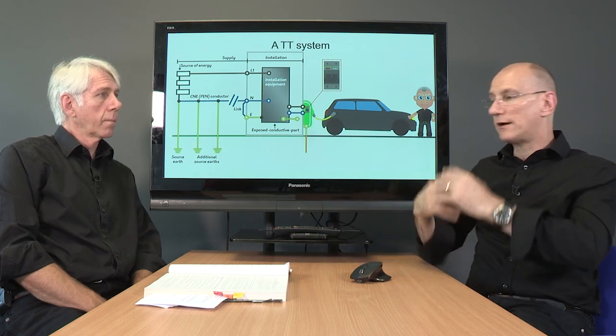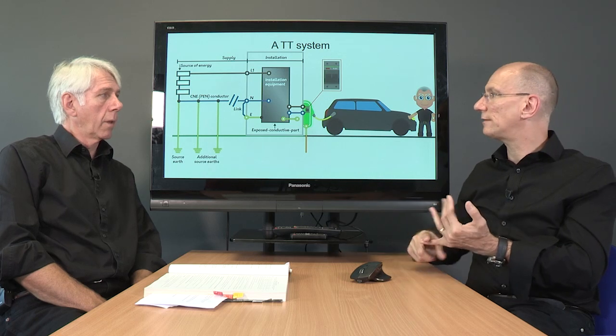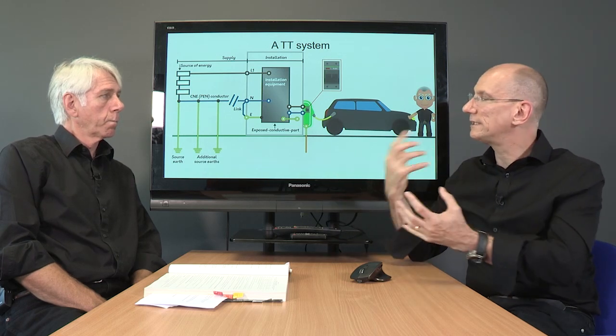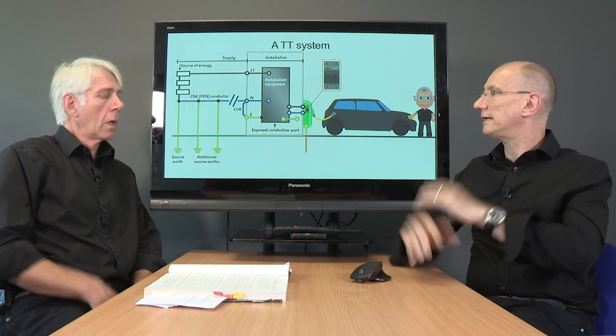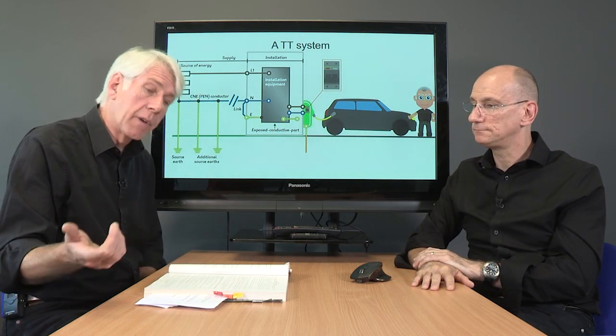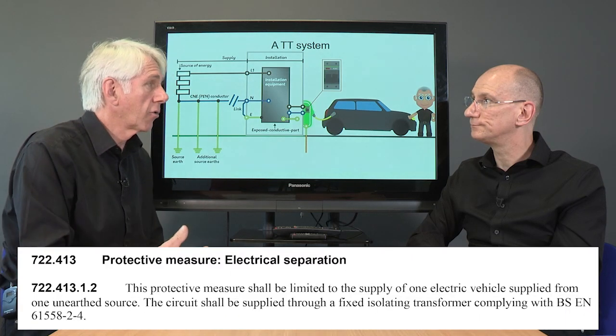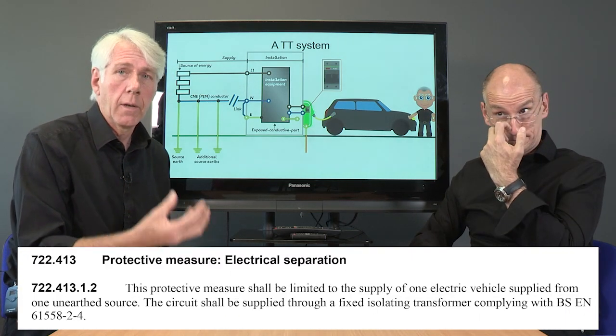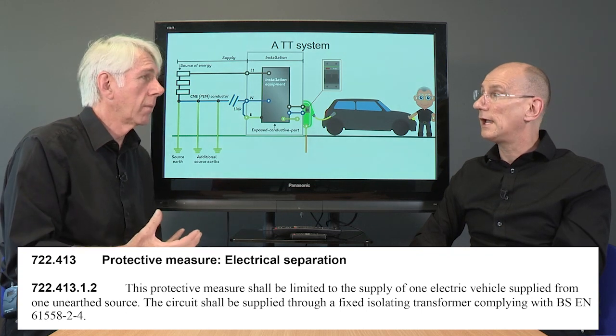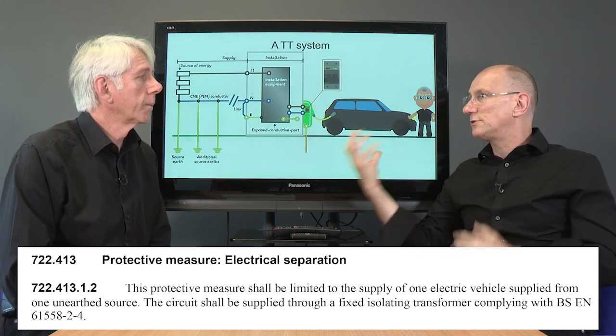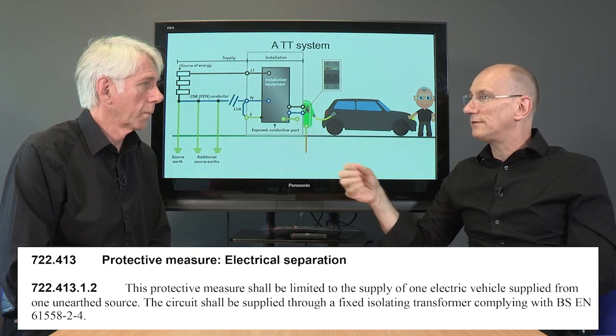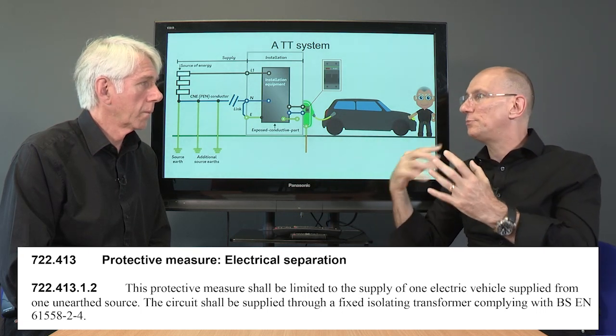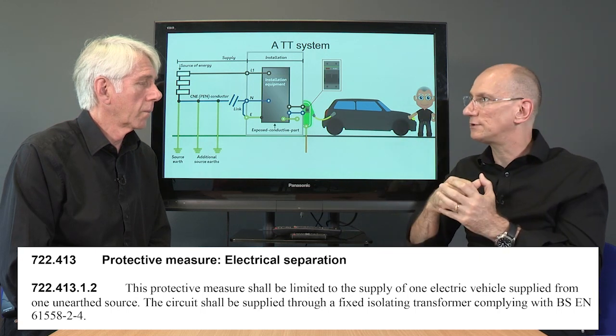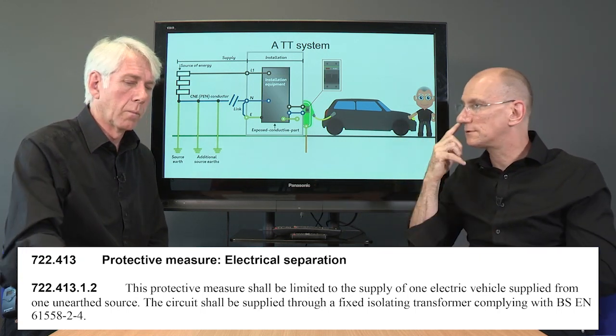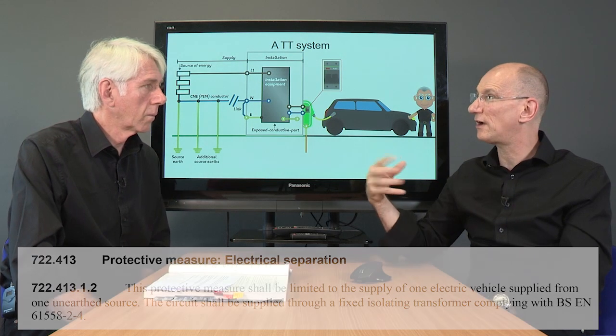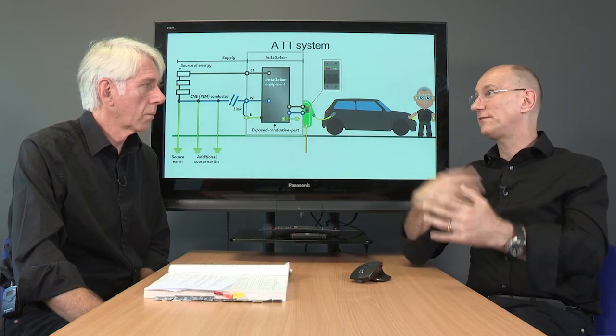So it is an option, but there are other issues, as I've covered and we've talked about, the proximity and the corrosion and the maintenance and side of things like that, and obviously banging in. For the sake of completeness, as we mentioned in the other video, there is a fourth option, which is the isolating transformer. But we said to get a decent current would be an expensive and quite bulky option. Yeah, the isolating transformer, starting at the basic sort of 16, 18 amps level, I think is around about 180, 200 pounds, just for the kit. I mean, obviously you've got installation costs on top of that, but you start going up to a 32 amp and you'd be sort of several hundreds of pounds. And if you want a super fast charge, 3-phase, 63 amp, you could be 1,500 pounds.